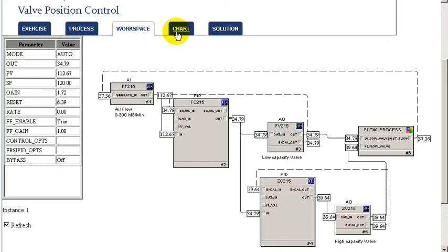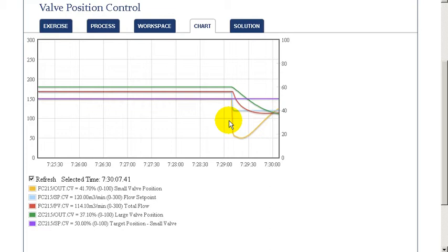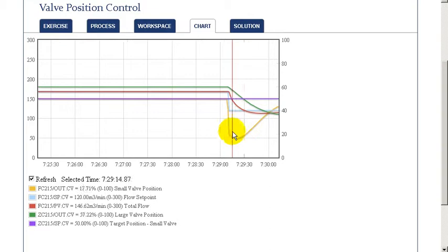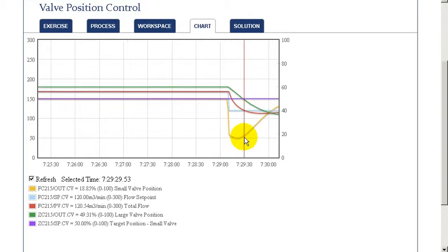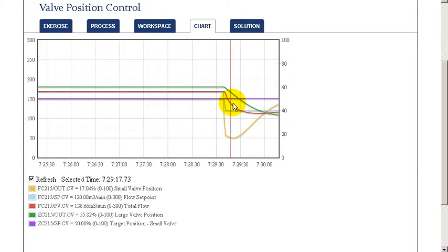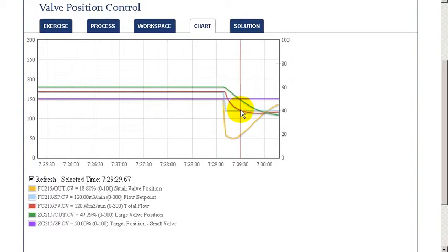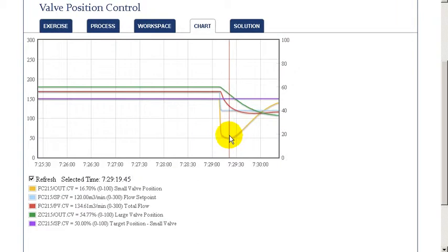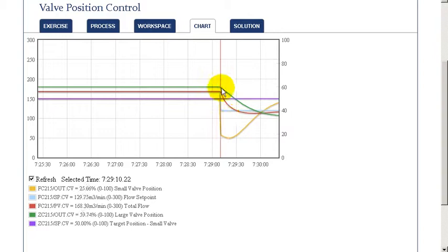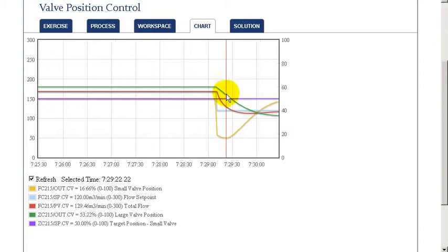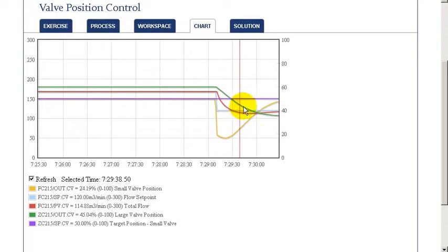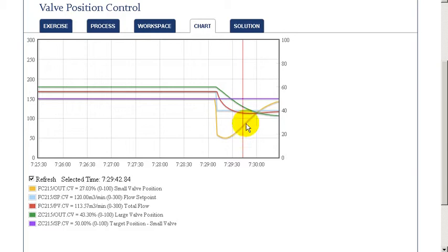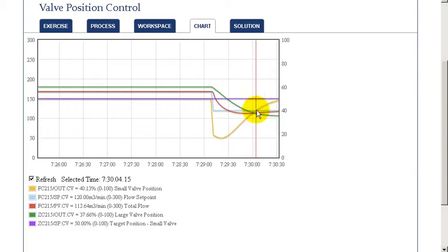This is better seen by looking at our chart where we change the flow target. We notice the smaller valve takes immediate action to achieve our target. Also, the larger valve gradually starts to change to take over or make up for the change made by the smaller valve. This allows the smaller valve, then, to go back to its original target value.